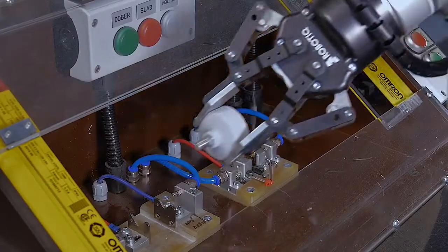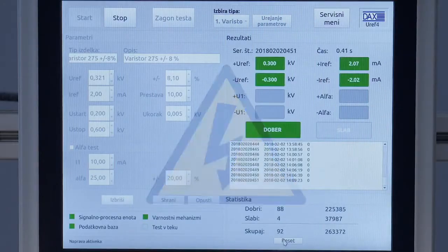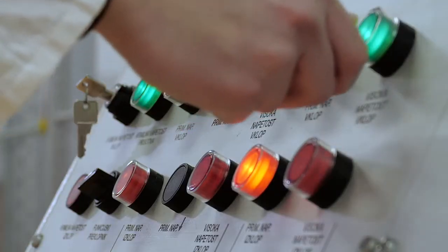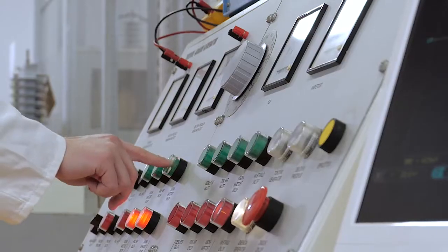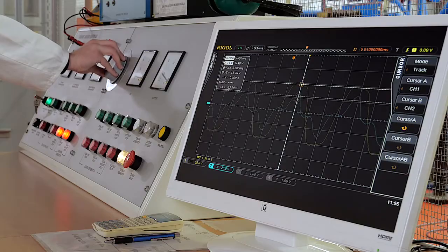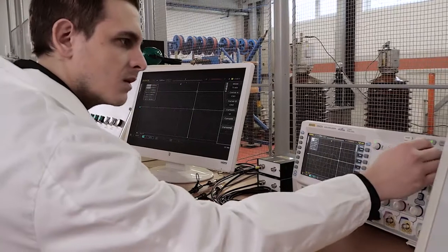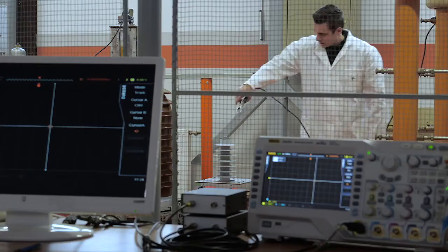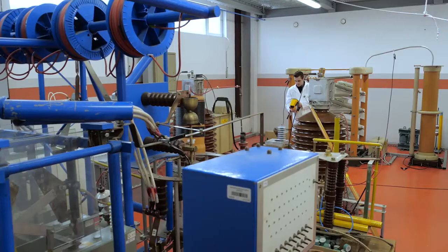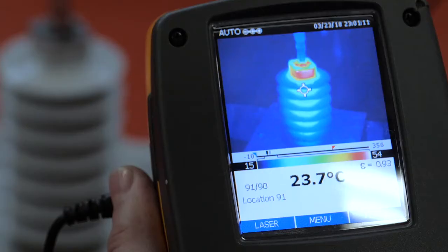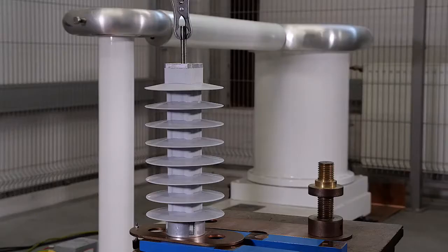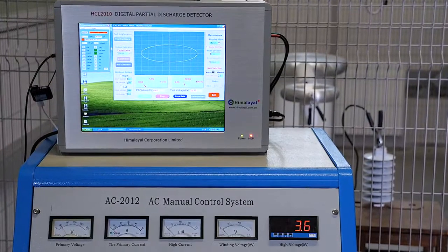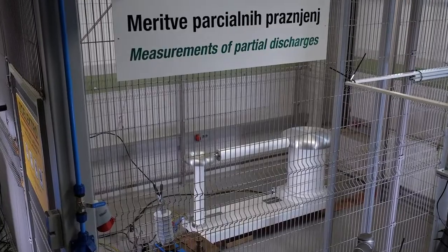The low-voltage surge arresters are tested according to both the old standard and the standard from 2011. We have our own high-voltage laboratory that enables us to run tests with alternating voltages of up to 220,000 volts and 1.2/50 microseconds wave-shaped lightning impulse voltages up to 500,000 volts. The lab allows us to run most standard tests on medium-voltage surge arresters. Our testing environment for low-voltage surge arresters uses a 10/350 microseconds wave-shaped lightning impulse current up to 50,000 amps. The laboratory's latest acquisition is a digital device for testing partial discharges on medium-voltage surge arresters.